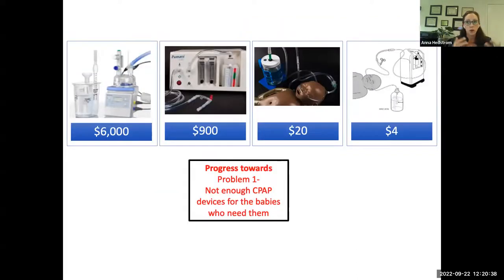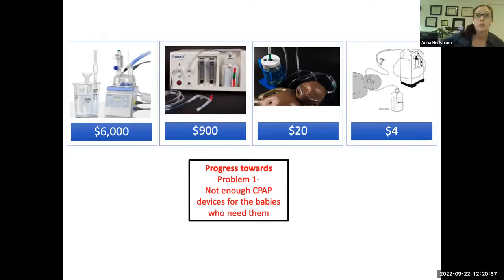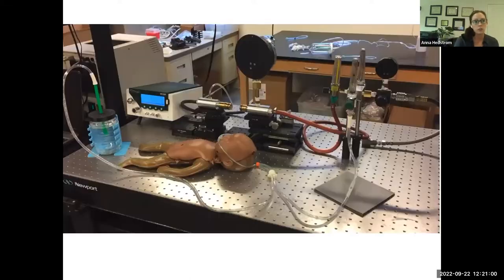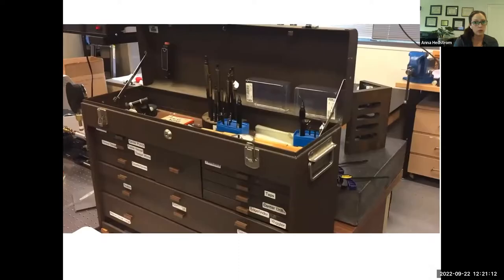There's now progress toward more affordable devices. This PATH device probably costs around $20 to manufacture — it's not on the market yet, and things always end up more expensive than you think, but either way well below $900. As you can tell, this device, although it won't be marketed this way, could be cleaned and reused, which is what actually happens in these settings — as opposed to commercialized devices that aren't always cleanable.